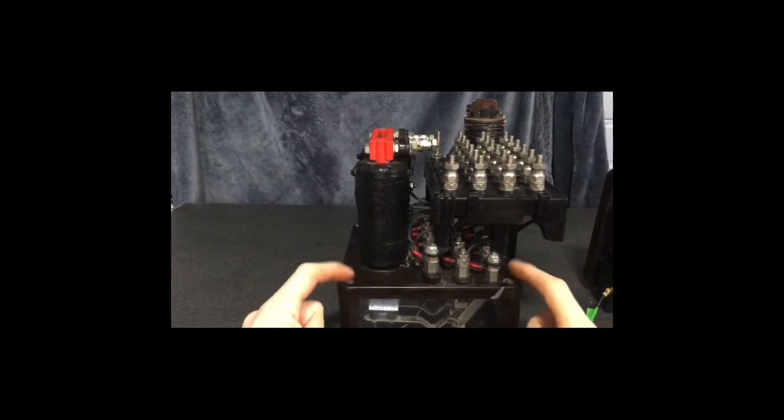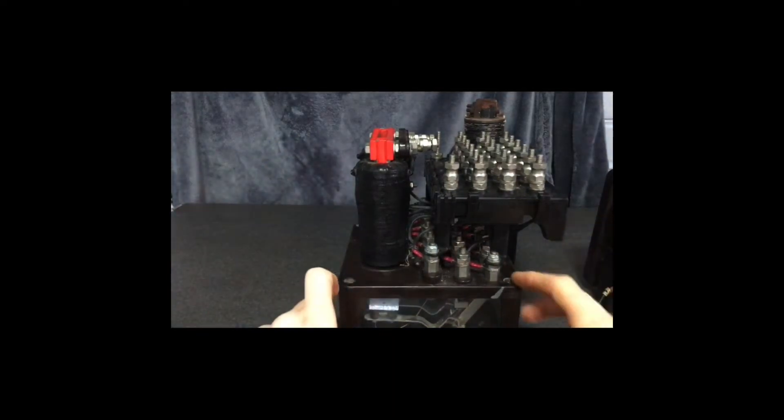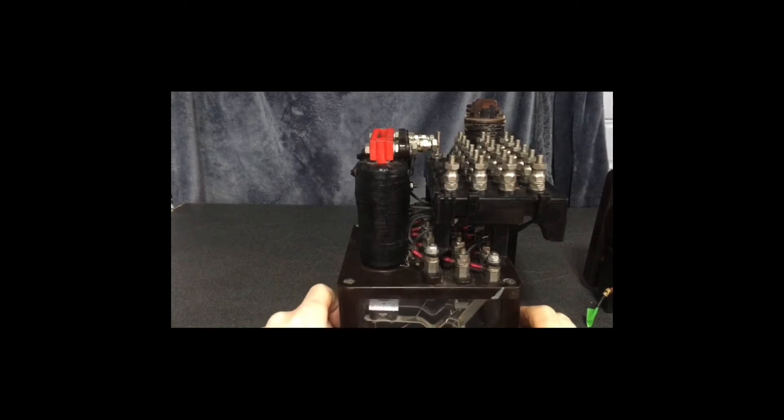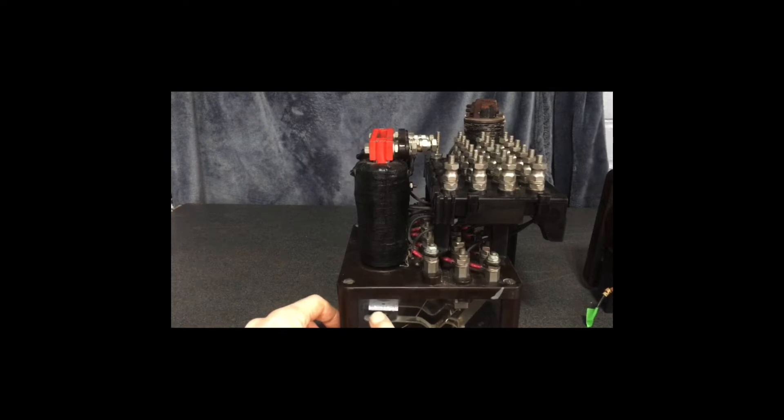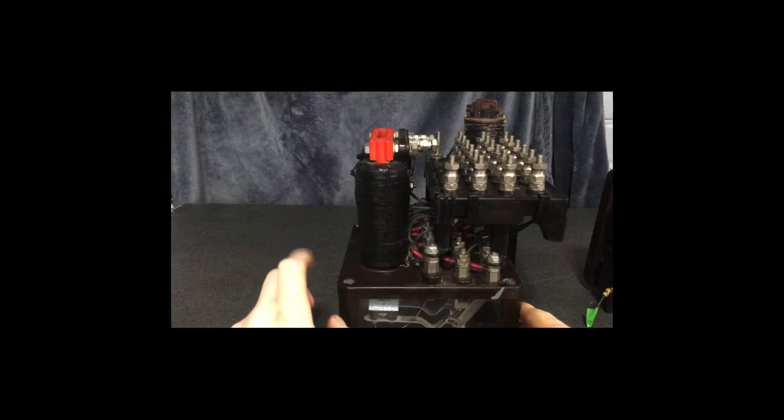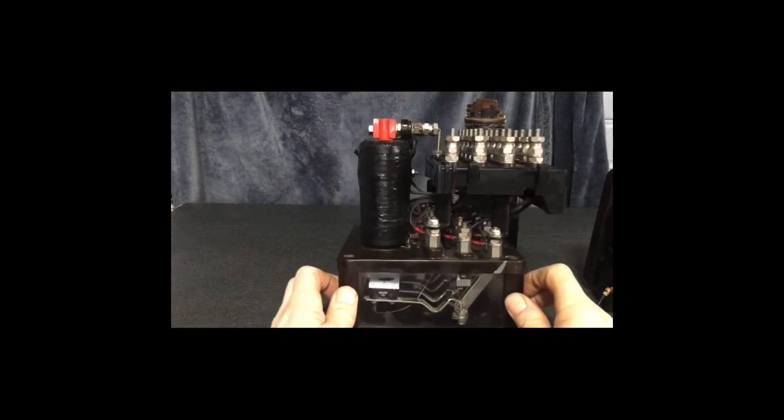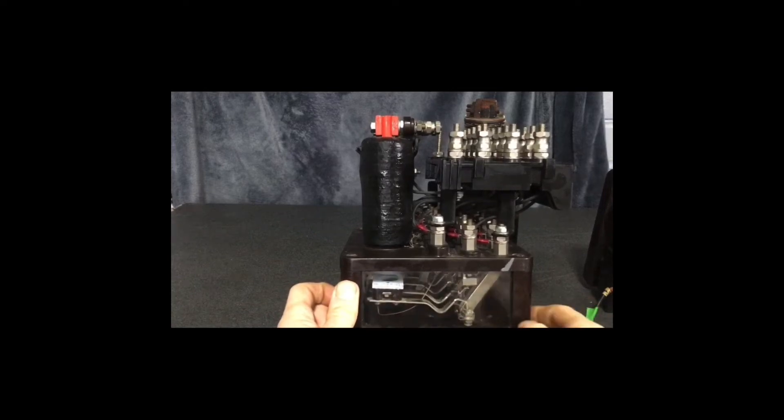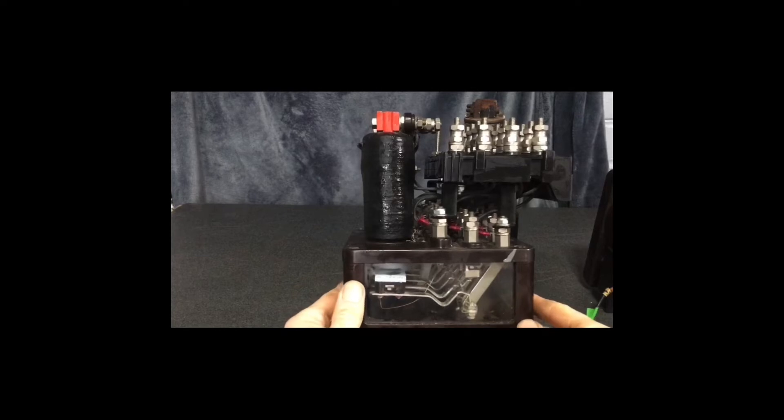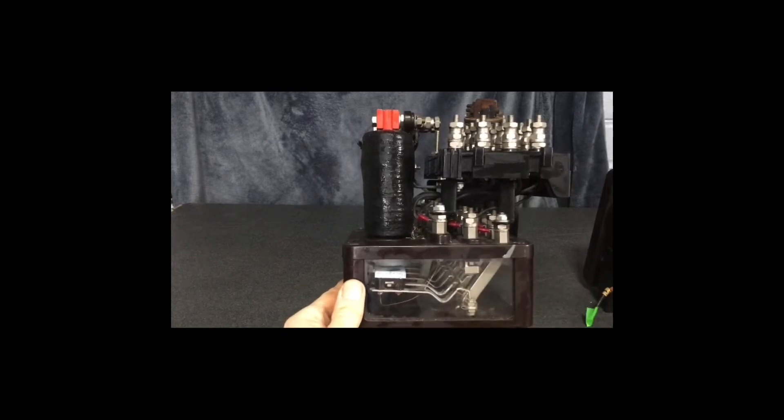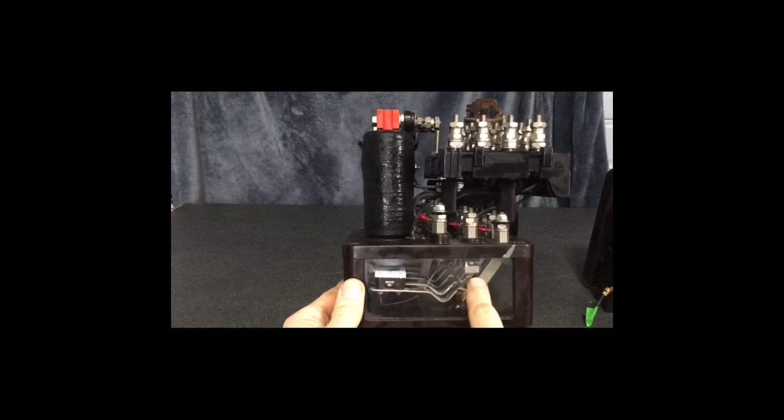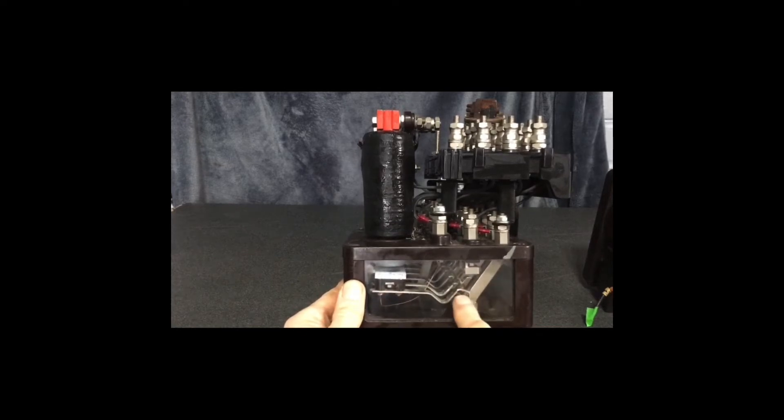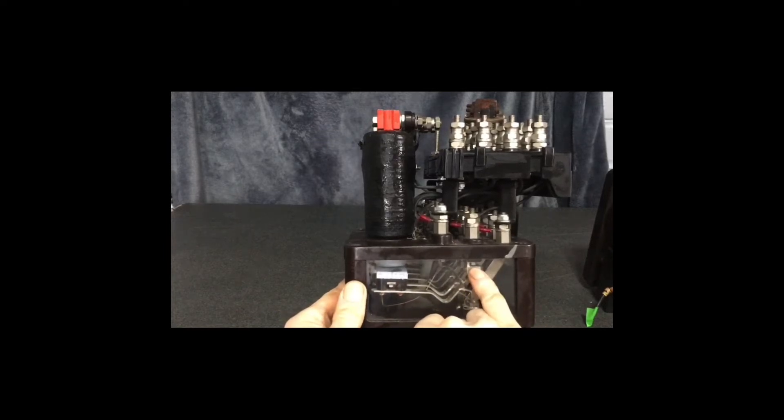They are sealed. They have four screws in on the corners, so this top does come off, and there's one of them sealed with like a resin seal from the manufacturers. You'll notice this one's got a little bit of dampness in it over time, and a little bit of verdigris there on the magnetic plate of the armature, but it's not affecting it. Everything else inside, they're all dissimilar metals so they can't weld together. You'll see one of the plug-in relays later that's got heavy-duty contacts on it for high voltage shifting. These don't shift much voltage, but they have carbon blocks and then silvered metal contacts so you can't weld them together.